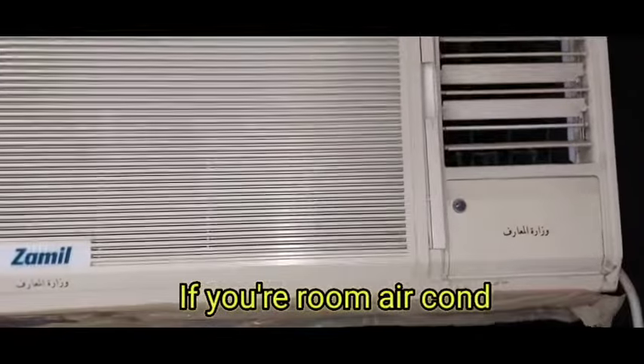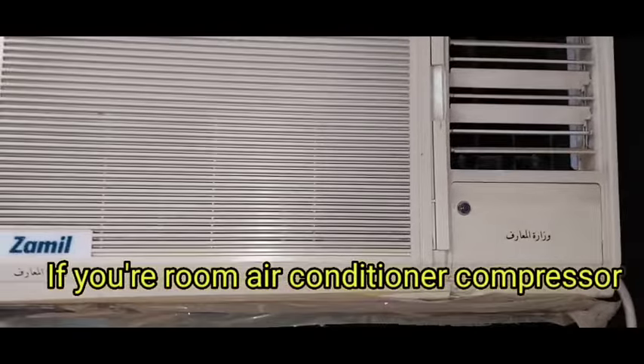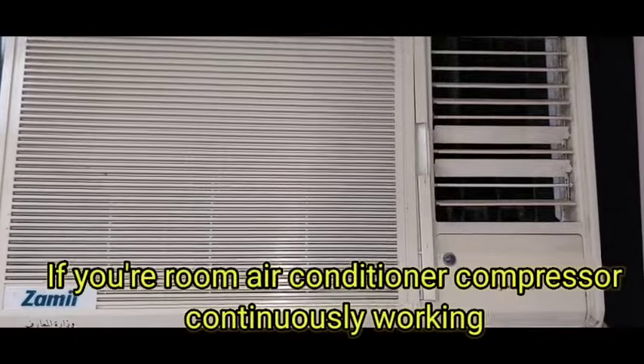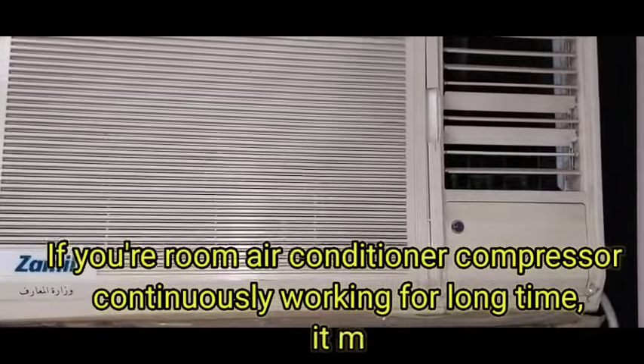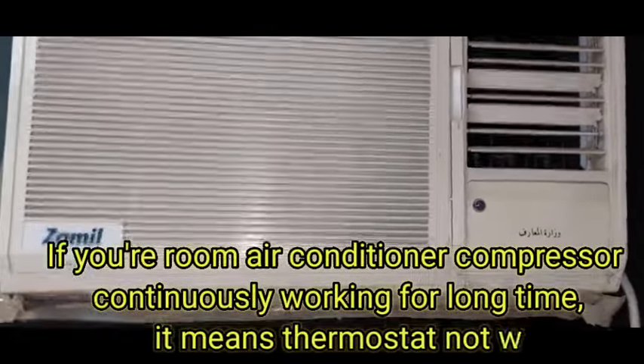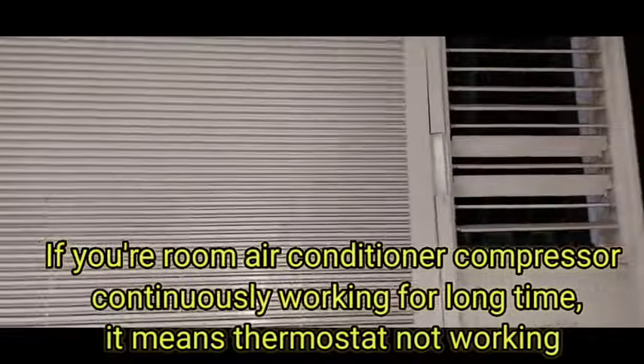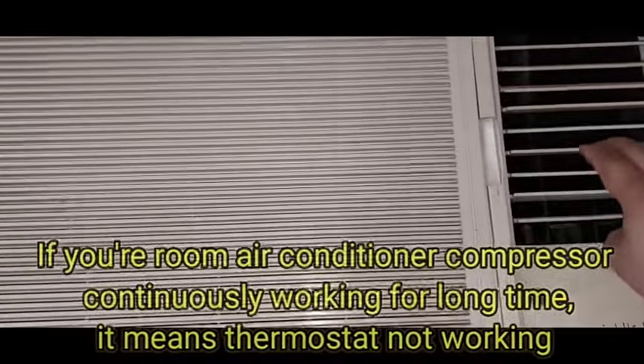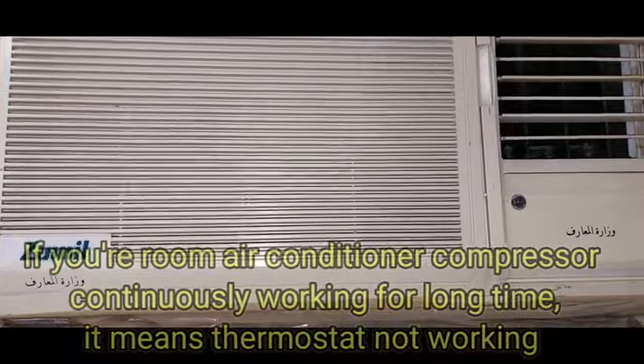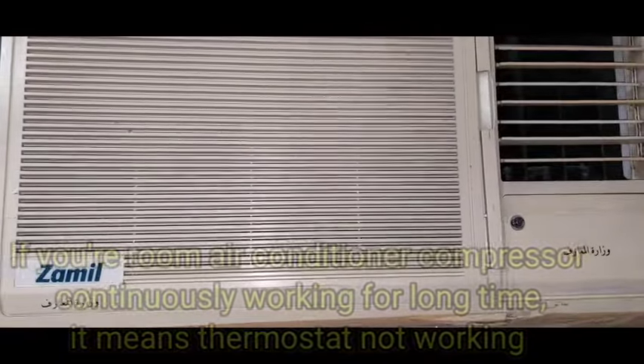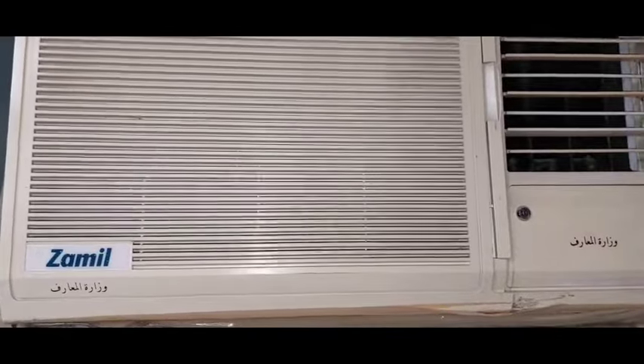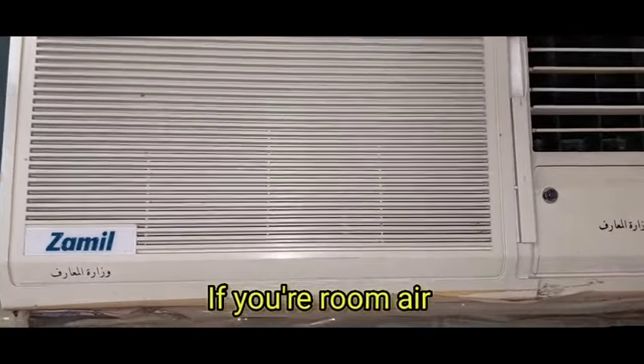We are going to fix the thermostat. This room air conditioner, or you can call it a window AC, is a 1.5 ton 2003 model, which is still working well. But what I observed is it's not tripping at your set temperature. Normally when the thermostat reaches the set temperature, it will trip: the fan will keep running, but the compressor will stop. But in our case it's not happening.